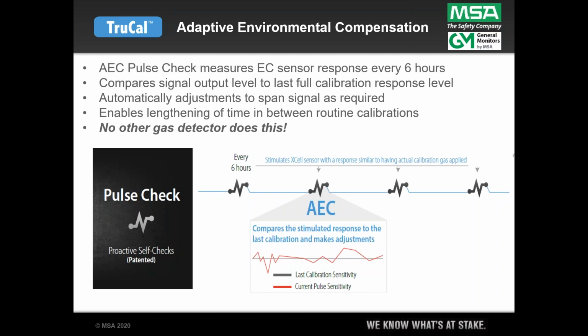If it's good, it says, hey, we just checked ourself with a pulse check, I stimulated it with a similar response, and we're spot on. But if there's a little bit of degradation, say the sensor's been working and maybe got exposed to some contaminants, it will automatically respan that sensor to match the last good calibration. So what's the benefit for users? It lengthens the time between routine calibrations. It is amazing, to the point where it would be possible to reduce calibrations on these devices down to once a year, which is incredible. I don't want to say that's the case in all situations, but it's a possibility. It's a diagnostic that ensures reliability and availability of the instrument all the time.